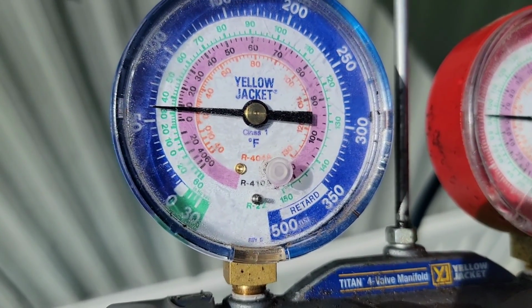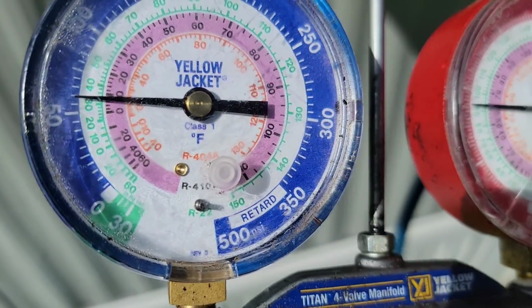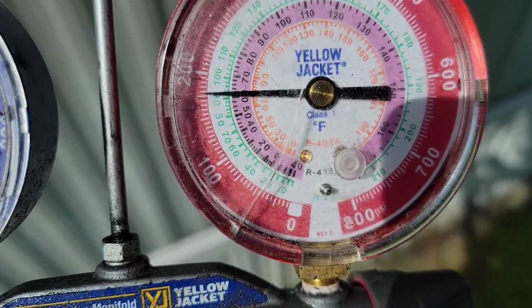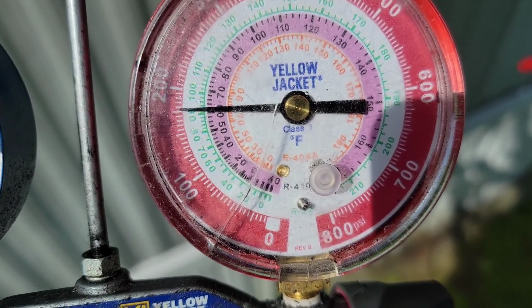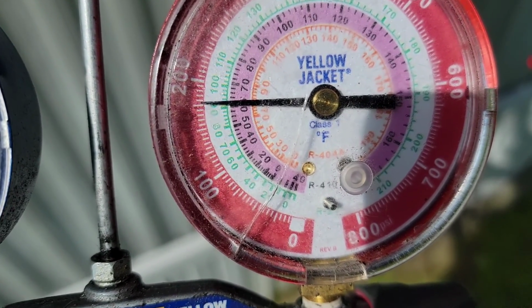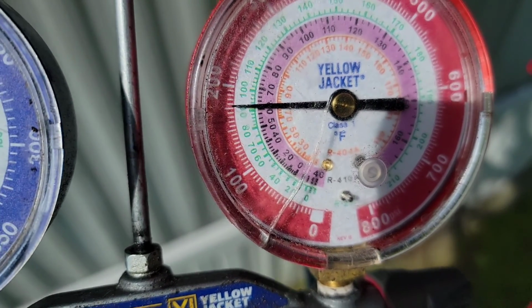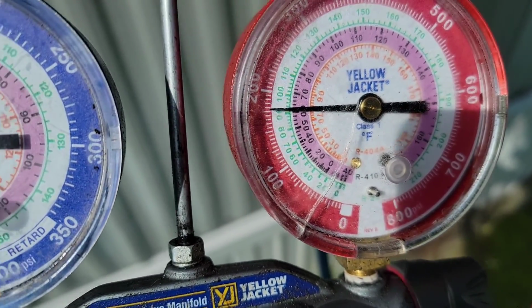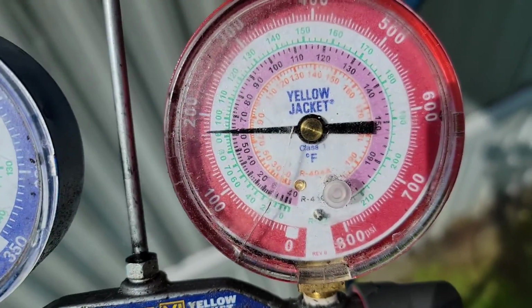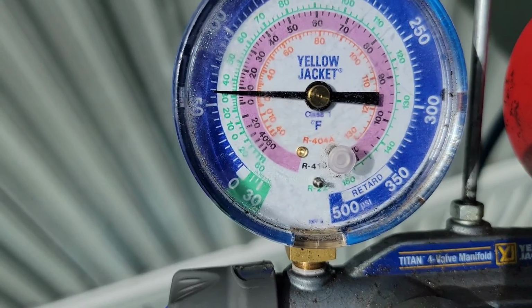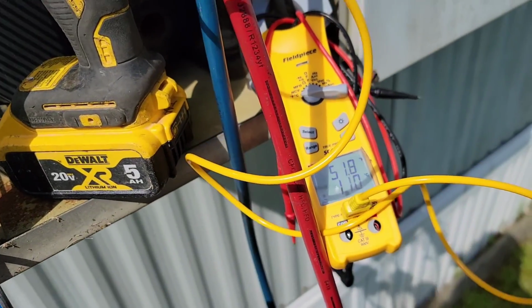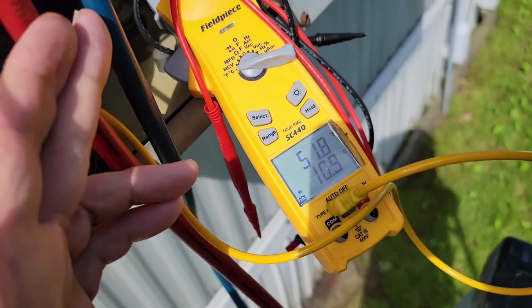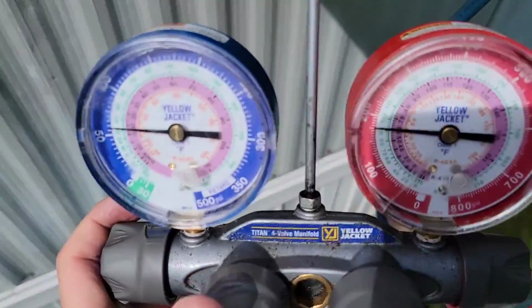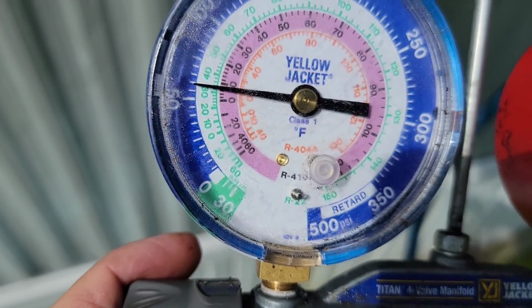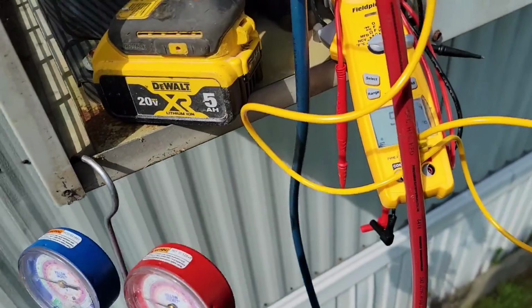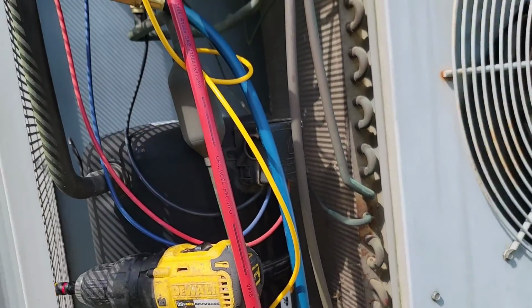Suction pressure is 60. So saturation temperature is about 33, 34. We've got our head pressure at 180, so that's pretty good. Saturation temperature is around 92, 93, 94. So we got a 60-degree difference between saturation temperatures, and pressures are looking pretty good, 70 degrees inside. Now the suction temperature's dropped to 51, so 51 and 31, 20 degrees of superheat. We're reaching the 10 to 15. So this unit is just about charged perfectly.